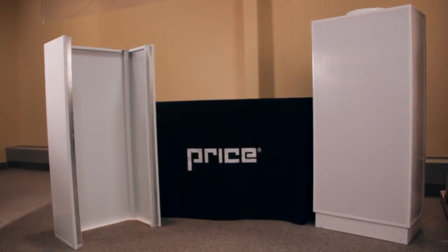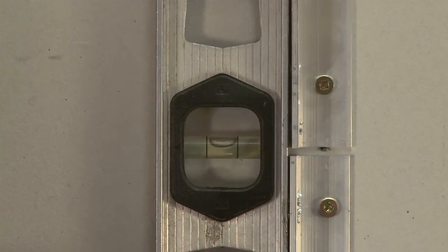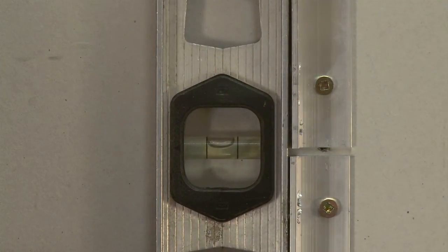If the diffuser features a duct cover, the additional length of angle that protrudes from the top of the diffuser will ensure that they connect properly and will minimize unsightly gaps. All angles should be mounted at the same time for the diffuser and the duct cover. Use a level to ensure that the angles butted to each other are properly aligned.